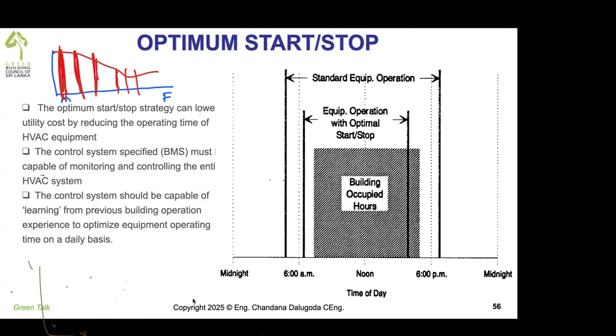But your air conditioner, you run Monday at 6 o'clock. Tuesday 6 o'clock. Then 7, 8, 8, 8. So 6 to 5, 6 to 5. You might think, oh my God, instead of running 8 to 5, you are running 6 in the morning to 5 in the evening. But thermal storage shows the week's energy demand is less than running 8 to 5. You don't believe it? You'll have to do it. One of my installations just concluded at Sampath Bank head office, Union Place. We do this. Tremendous energy savings.